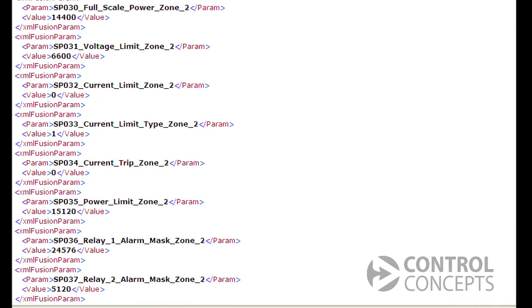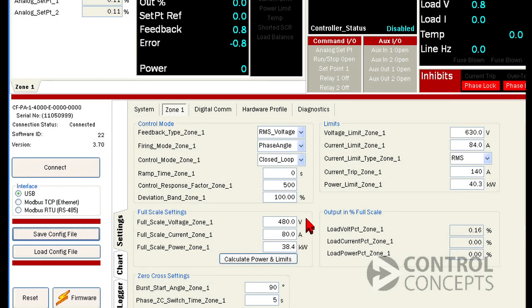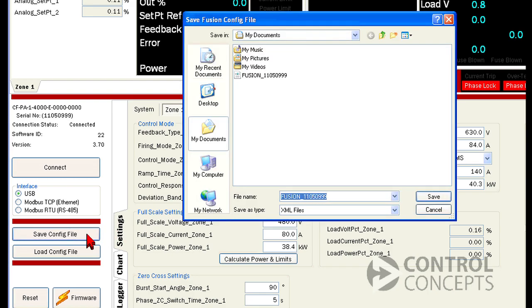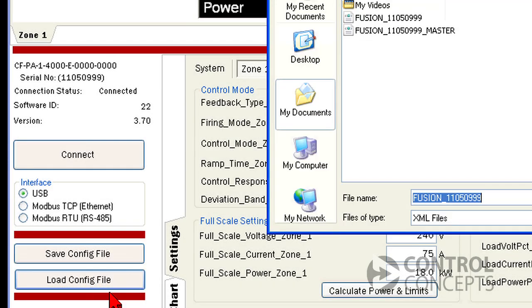If you have multiple controllers with identical hardware parameters, you can load the same config file to all of them, like a template. So for example, here I've created a master config file and I can load it to keep multiple controllers running with the same settings.